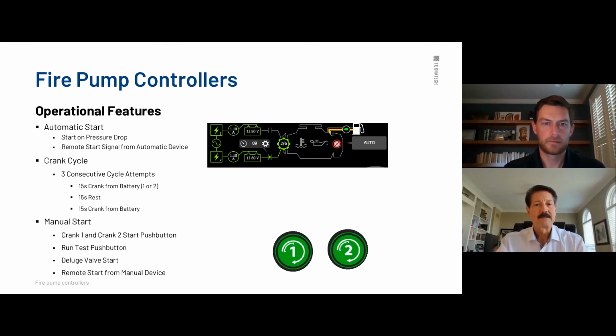It'll rest for 15 seconds. It'll then crank on number 2 for 15. If it doesn't start, it'll rest again and go to crank number 1. And ultimately what happens is, by code, you're going to do this 3 times on each side. And if after 3 cranks on each, crank 1 and crank 2, after a 15-second rest in between, it fails to start the engine, you will have an engine fail to start. That's a rare situation, but that's part of what we do when we do the testing on commissioning.